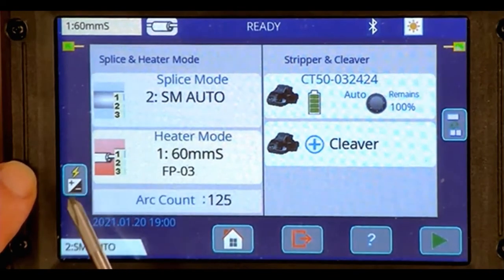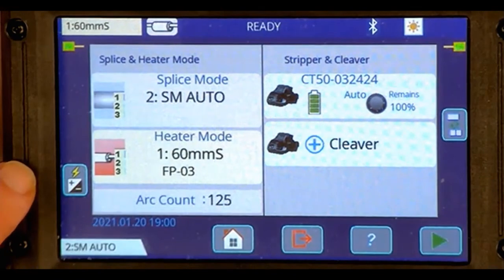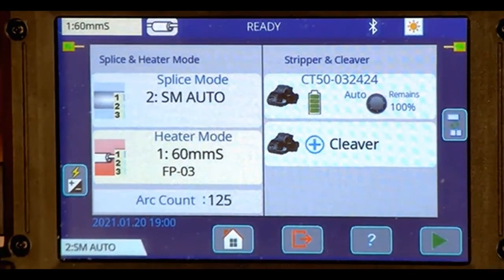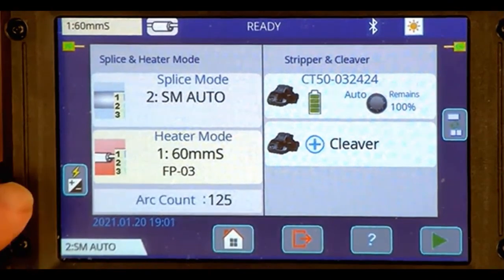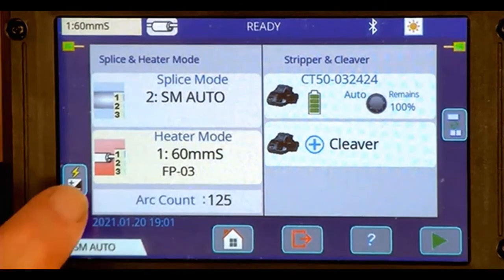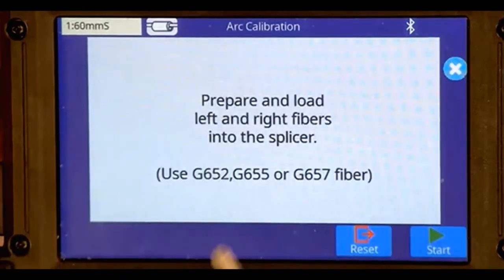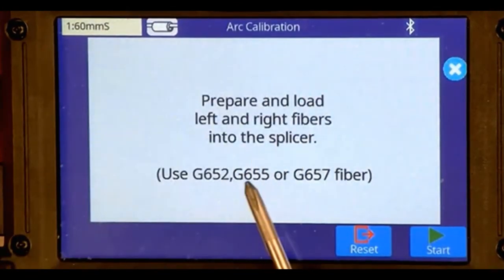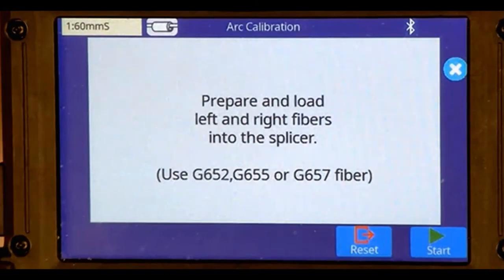This is to calibrate the arc power, so I don't have to go into my menu to find my manual arc calibration, the one I've recommended you do every day before you splice. From the main screen, I can just press that, and now it's telling me to prepare and load left and right fibers. It's already opened the wind protector and is ready for me to load the fibers.